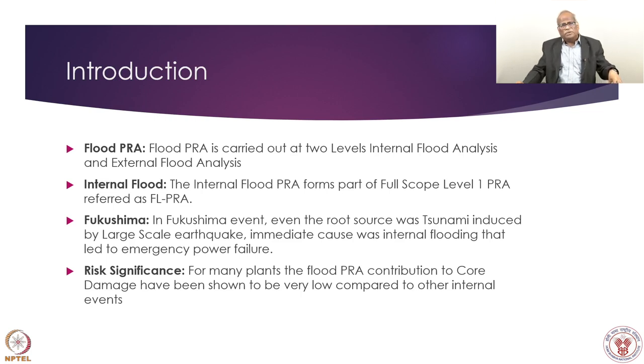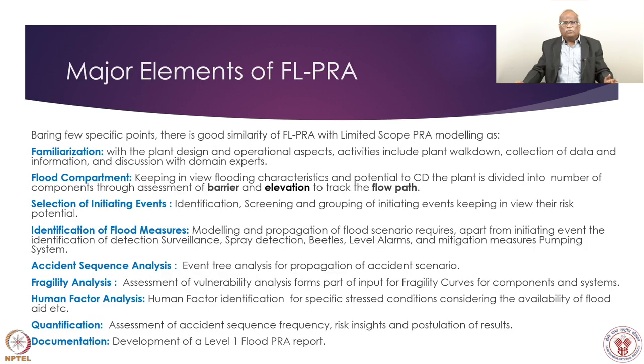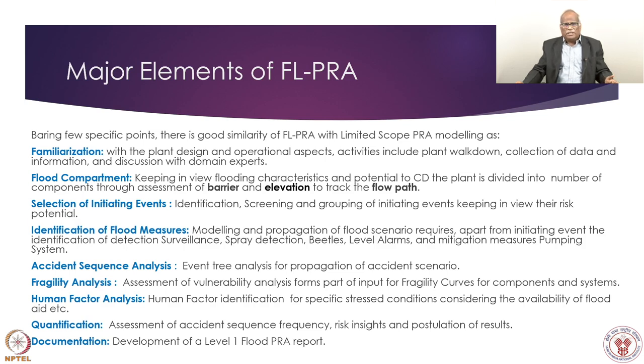In Japan, seismic is one of the important aspects for safety consideration. Now, what are the major elements of flood PRA? Many items are similar to level 1 PRA: familiarization with the plant, familiarization with the different flooding systems provided, and identification of different points which are potential for flooding to occur. That leads to the initiating event. In flooding, other than level 1 full scope PRA, the special point is dividing the plant into compartments.